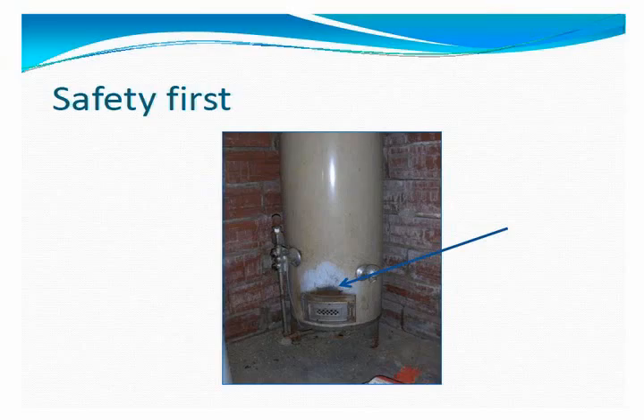First and foremost, we always talk about safety in our presentations, whether it's a public presentation or one of our internet webinars. This is an antique water heater that had obvious signs of backdrafting and fire going the wrong direction. That probably came from a venting issue. Maybe there was some kind of a negative air pressure issue in this mechanical room. This unit has long since been out of service, but we can see some obvious signs of burnt paint and other things missing. That's a good indication that there's a problem. If you see that in any water heater, you need to have a professional person come out and investigate, and let's see if there can be some things that can be done to correct that problem.